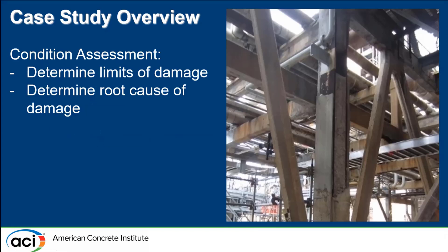The first part was conducting a detailed condition assessment: mapping out where structural steel was exposed, where welded wire reinforcing was exposed from the fireproofing, and defining why the spalling was occurring. In this case, a cooling tower located downwind was contributing acid overspray impacting the concrete surfaces. There had also been an explosion in the past that caused some cracking. We wanted to make sure we were addressing these items to maximize the durability of the fireproofing repair.